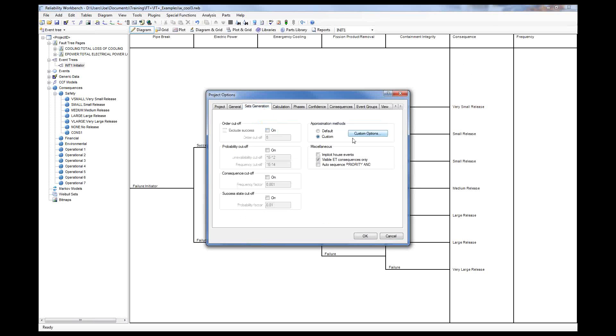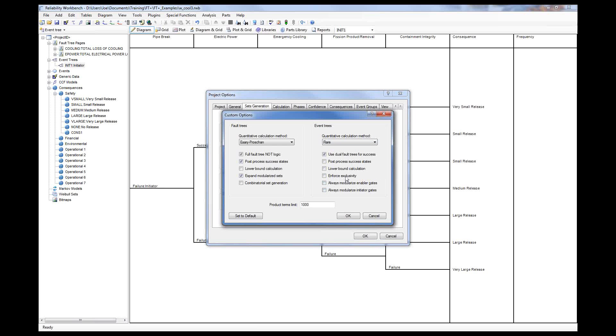Before I run the results, let me check these project options. Modularization has to do with solving branches independently. Generally speaking, certain analysis types assume your enabling events should be independent — but that's not always the case. For instance, electric power and emergency cooling are not independent from each other. So I've unchecked these two options, which allows the program to recognize that they are dependent and adjust the calculations accordingly.